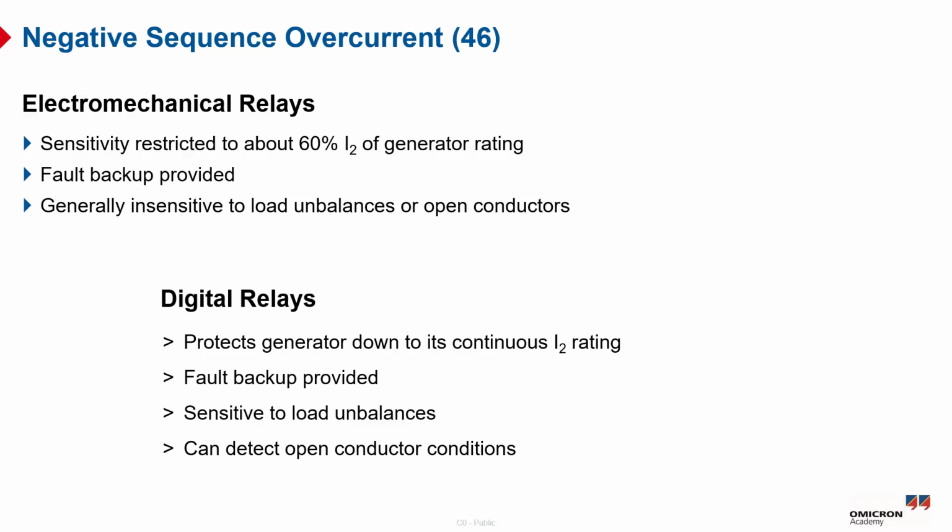In contrast, the electronic relays are much more sensitive, matching the generator's thermal I2 squared T curve and detecting low-level imbalances, and offering features like alarms, K-based time settings, and the memory of delayed reset. This memory ensures a quicker response if the fault appears or reappears before the rotor fully cools, improving the protection effectiveness.